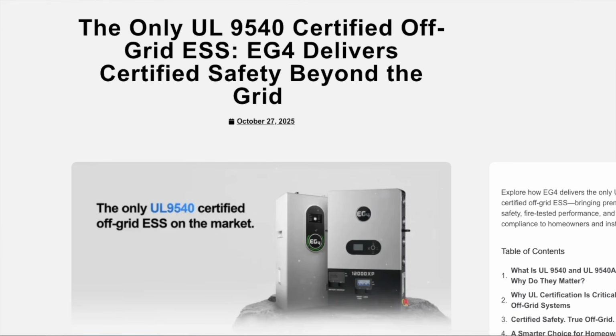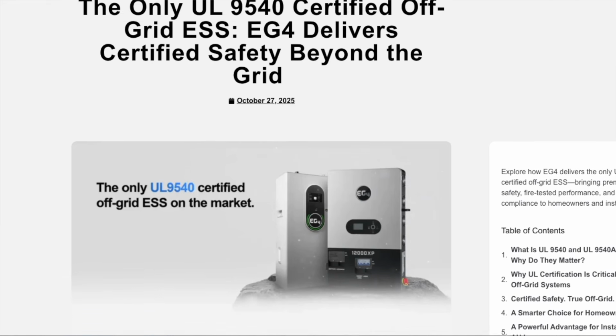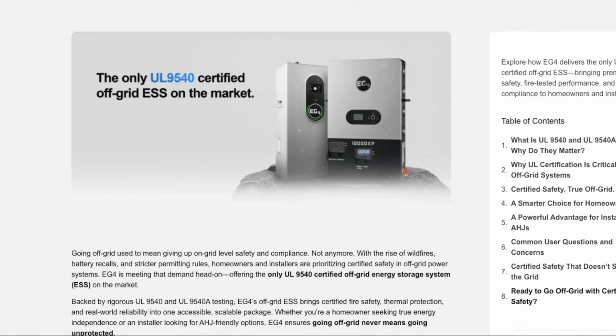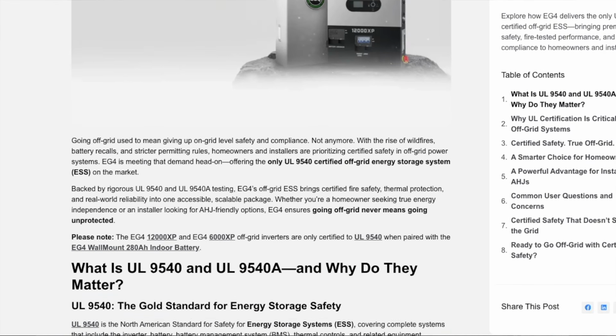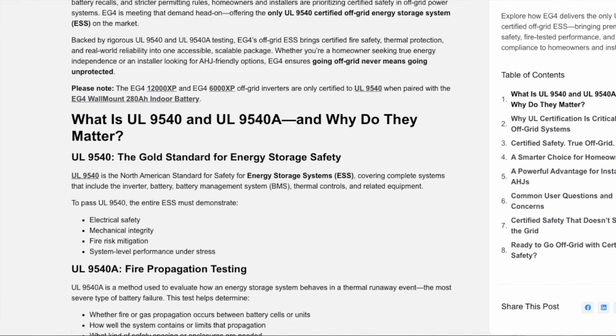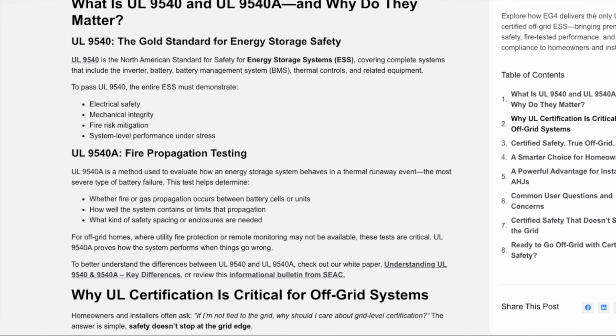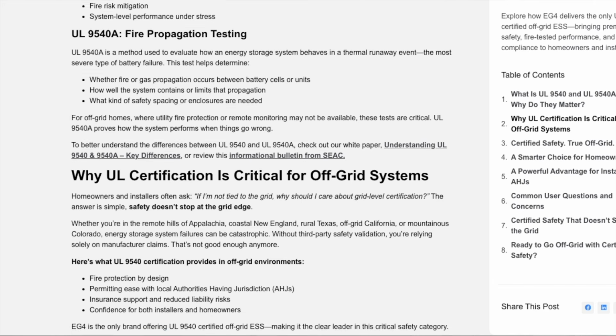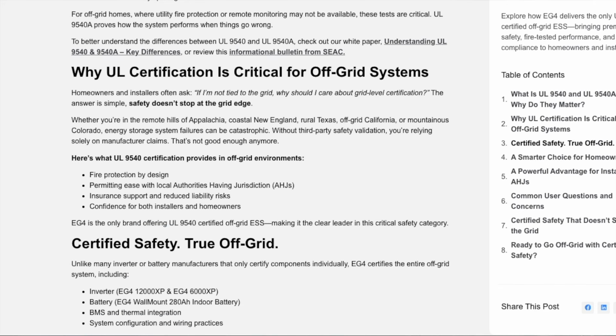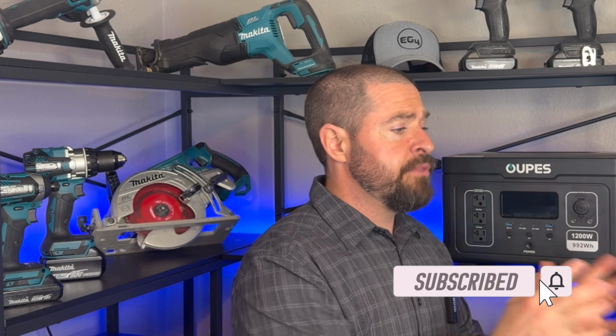On top of that is UL 9540A listed when paired with the EG4 indoor wall mount battery. Now, for a lot of areas, that UL 9540A listing doesn't matter, but in areas prone to wildfires or in just certain locations where your local inspector is strict, they want that UL 9540A listing. And that listing can only be obtained with a full system. So that is the inverter and the battery paired together, run through testing to confirm that the entire system is safe, is not going to cause a fire.